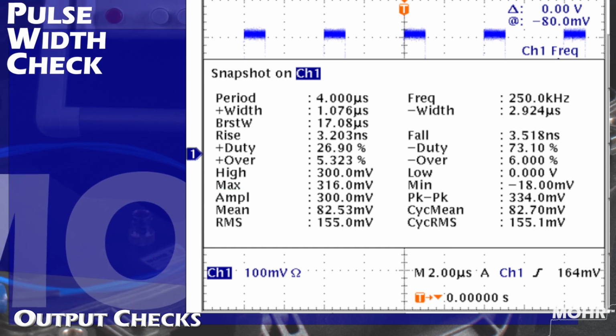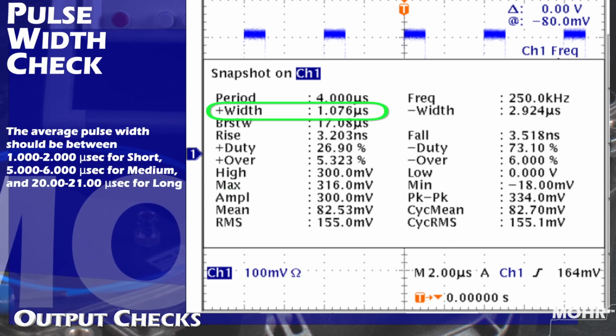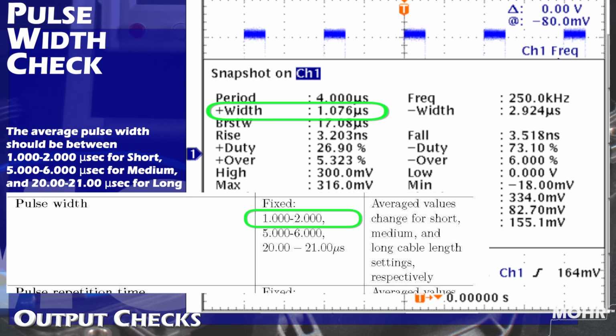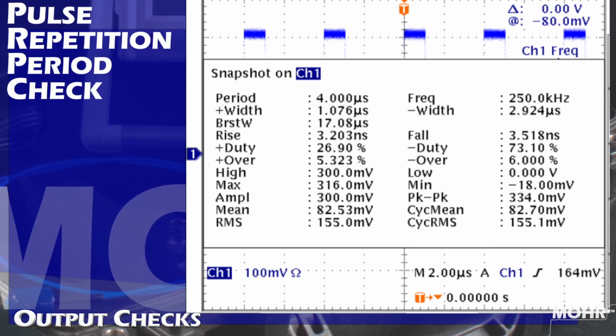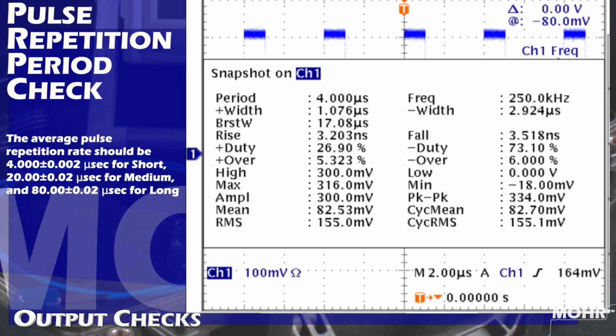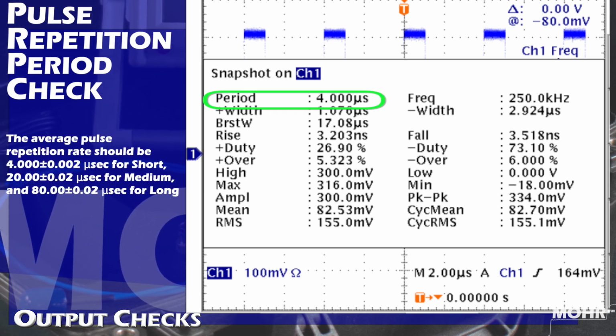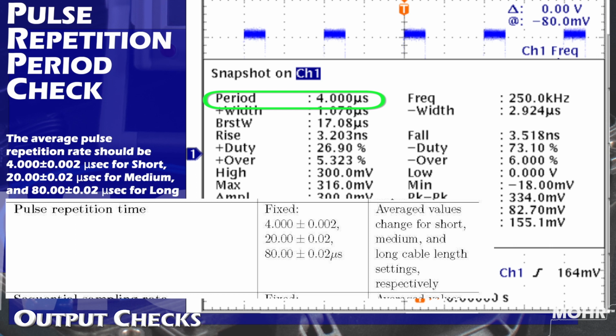For the pulse width check, pulse should be between 1 and 2 microseconds for short, 5 to 6 microseconds for medium, and 20 to 21 microseconds for long. For the pulse repetition period check, the average pulse repetition rate should be about 4 microseconds for short, 20 microseconds for medium, and 80 microseconds for long.